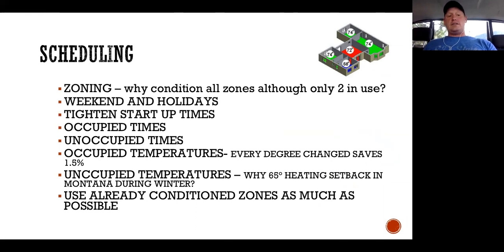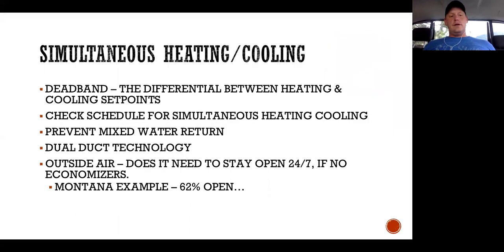Occupied times and unoccupied times are a big thing as well, especially in a colder environment. If you set your unoccupied heating temperature from 68 down to only 64 or 65, which I see a lot, that's still causing that boiler to run 24 hours a day at times. Being as aggressive as possible matters, facility managers know their buildings better than anybody else and know what that number should be, but being aggressive on your unoccupied temperatures makes a big impact. 55 heating, 85 cooling if you can is what EPA recommends. There are other things here I don't have time to go through.